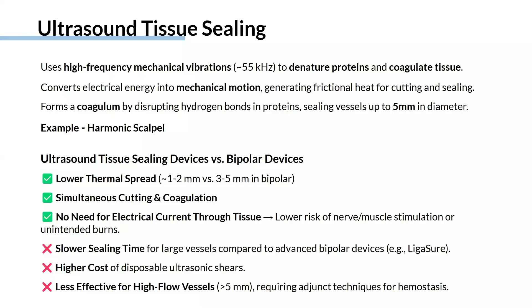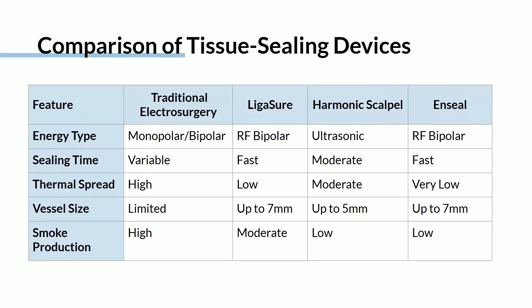Next, I have included a table that summarizes the difference between the different tissue sealing devices, which I think includes the important information that we need to know. So the basic differences have to do with the energy type, as we discussed, the sealing time, the thermal spread. It's higher with the traditional modalities versus the more recent, modern, sophisticated ones. The vessel size, again, the LigaSure and the Enseal can seal up to 7 millimeter vessels, the harmonic scalpel up to 5 millimeter. And smoke production, this is something that we didn't talk about very much, but traditional electrosurgery produces the highest amount of smoke compared to the harmonic and the Enseal that don't produce that much smoke.